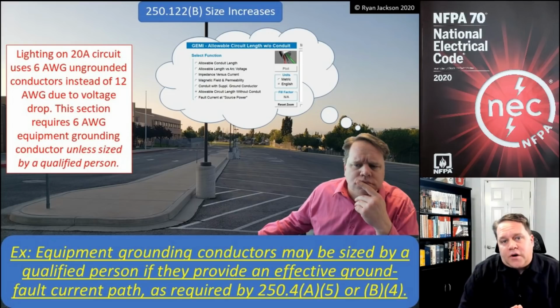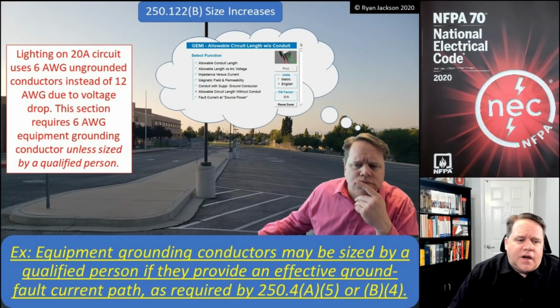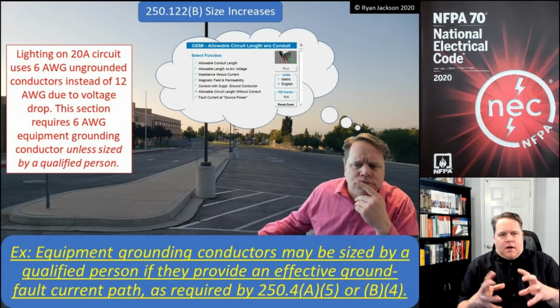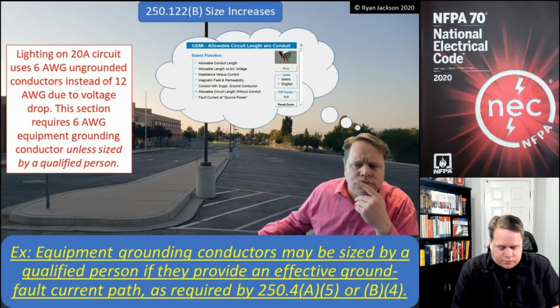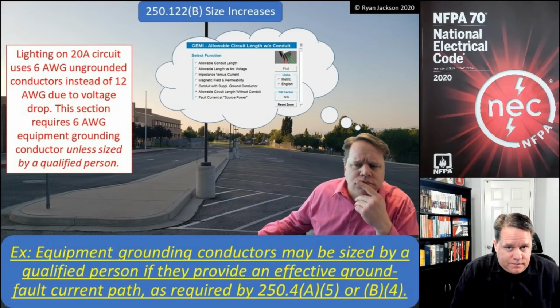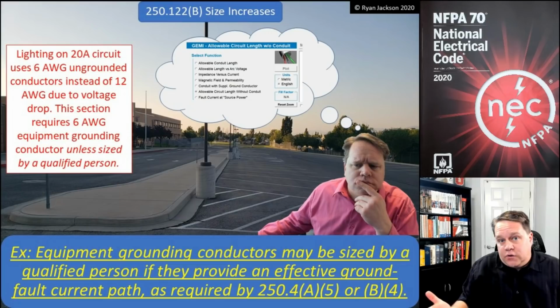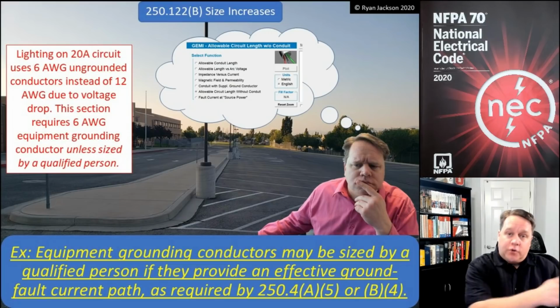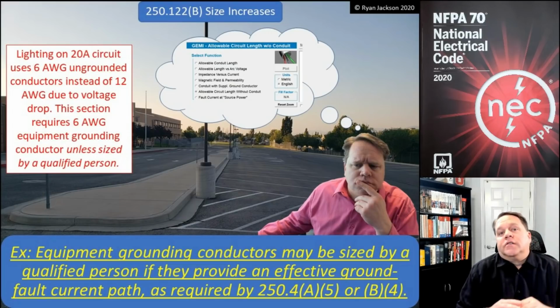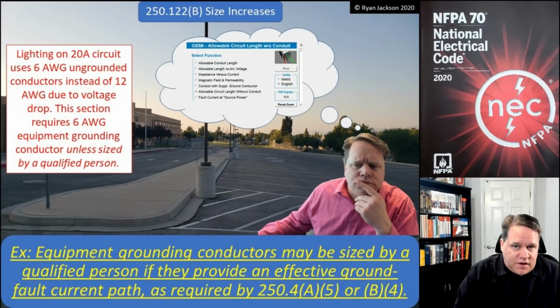It says, look, equipment grounding conductors can now be sized by a qualified person, not even an engineer, but a qualified person, if they still provide an effective ground fault current path as required in 250.4(A) or 250.4(B). Okay, so it's saying, look, at the end of the day, we need a safe installation. Right? That's what 250.4(A) and 250.4(B) both say. A for grounded systems, B for ungrounded. It says, listen, no matter what happens, we need a safe installation.